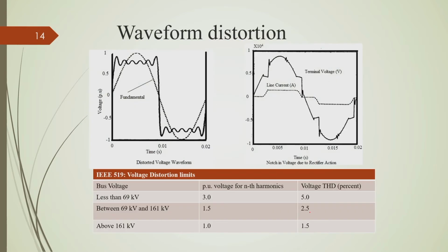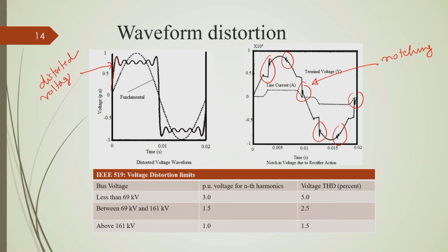Okay. I will show you the typical type of this notching here. So, these are the notches. You can see they are very short duration type of waveform distortion. So, these are notches, and this is basically a distorted type of sinusoidal waveform. So, this is a distorted voltage waveform, and we know we can translate a distorted periodic voltage waveform into a number of sinusoidal voltage waveforms by using Fourier series analysis, which will have a fundamental along with many harmonics.